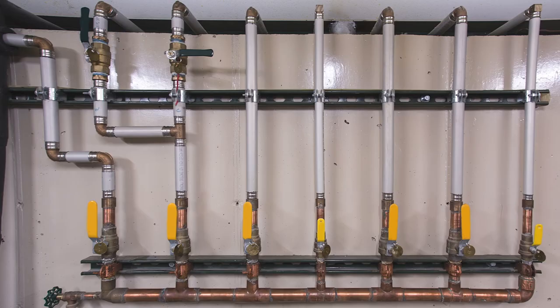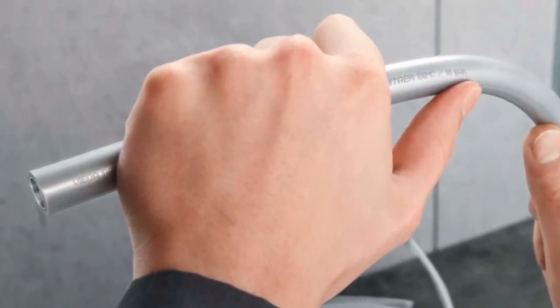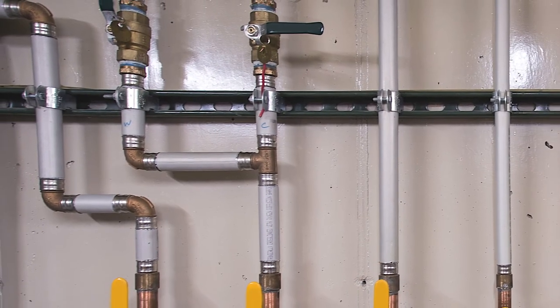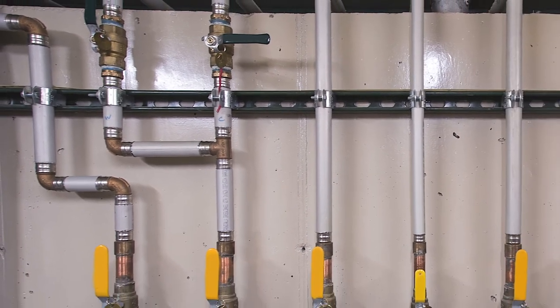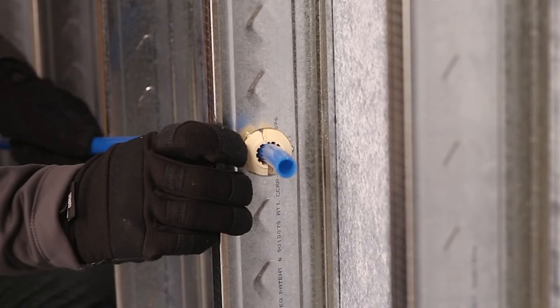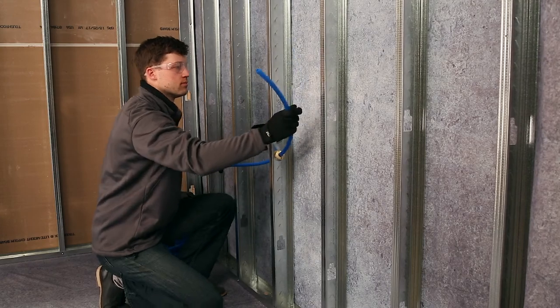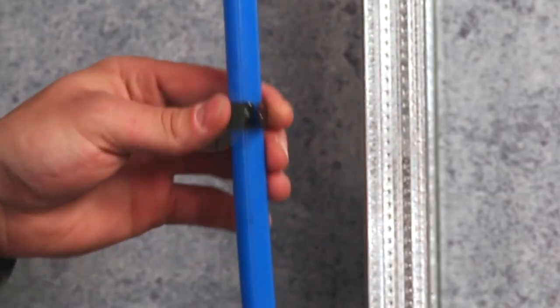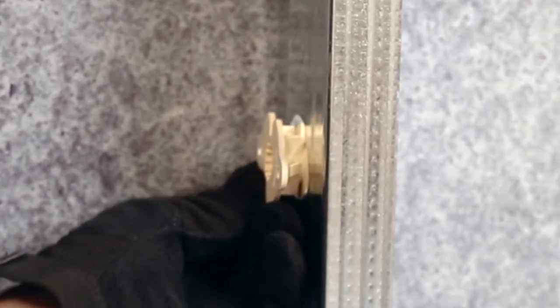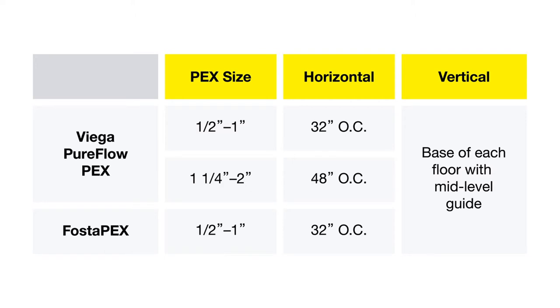The aluminum layer in FostaPEX reduces expansion and contraction so that it expands only 0.16 inches per 100 feet for every 10 degrees Fahrenheit of temperature change, making it ideal for locations where expansion must be minimized. Tubing should be allowed freedom to move slightly as it expands — do not clip it tightly into place or locate it where it will be tightly constrained. Use suspension clips or an approved plastic insulator where tubing passes through studs or joists where abrasion and noise is a concern. Viega PureFlow PEX tubing should be fastened at a maximum interval noted in the following table for horizontal and vertical support.